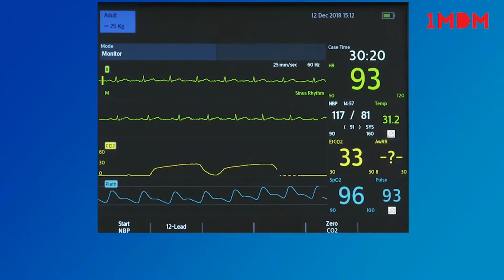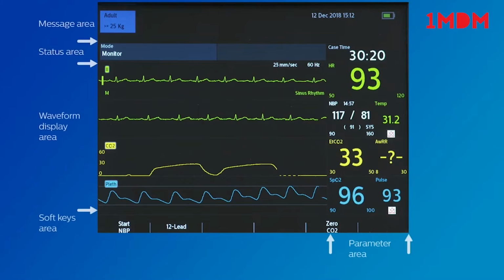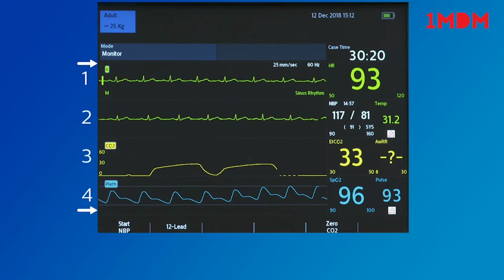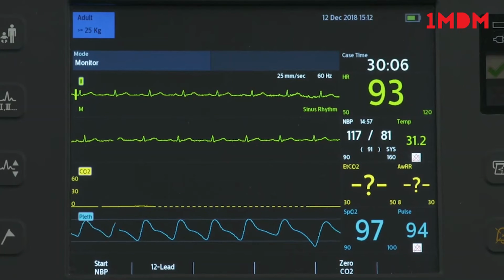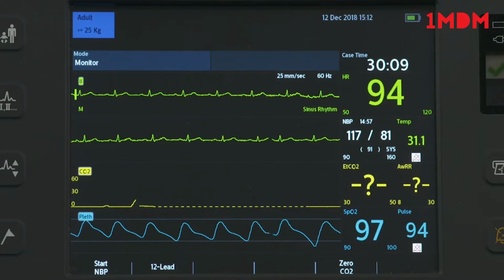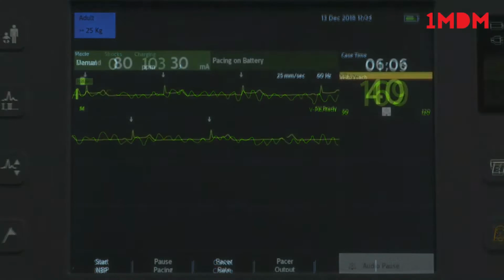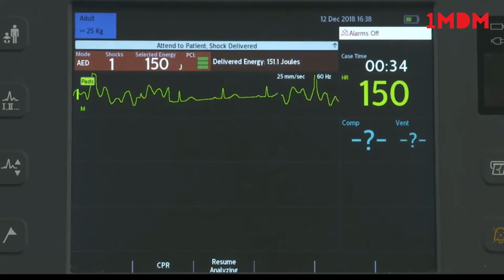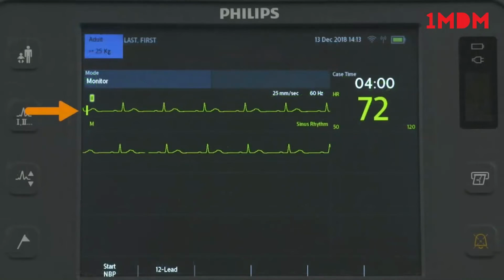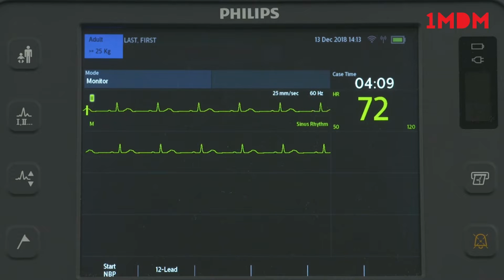The HeartStart Intrepid's display layout is comprised of 5 basic segments and is easily configurable. The display includes 4 wave sectors and a parameter area with related measurements. The HeartStart Intrepid is configured to populate each wave sector with a predetermined waveform when powered on in monitor, manual defibrillation, pacing, and AED modes. Wave Sector 1 will only display an ECG waveform, which is used by the arrhythmia, heart rate, and AED analysis algorithms.